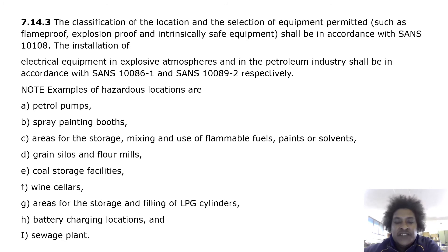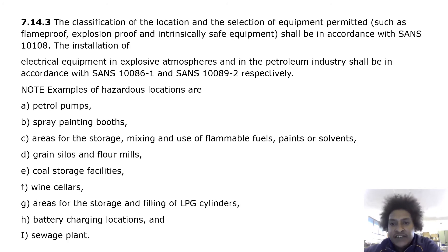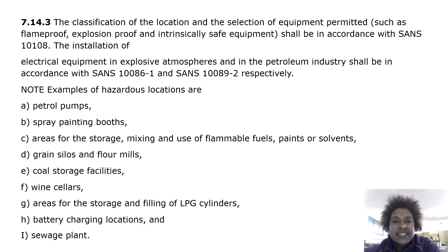The classification of the location and the selection of equipment permitted, such as flame-proof, explosion-proof and intrinsically safe equipment, shall be in accordance with SANS 10108. The installation of electrical equipment in explosive atmospheres and in the petroleum industry shall be in accordance with SANS 10086-1 and SANS 10089-2 respectively.